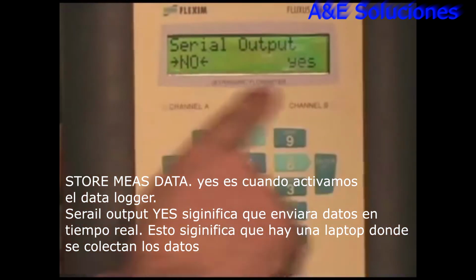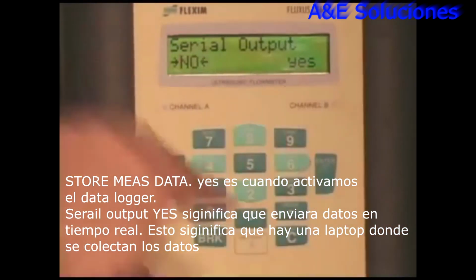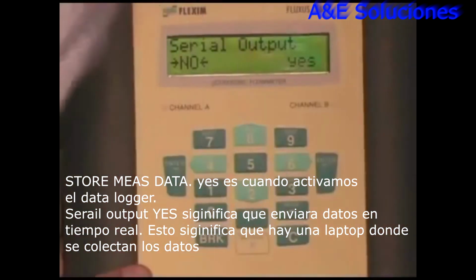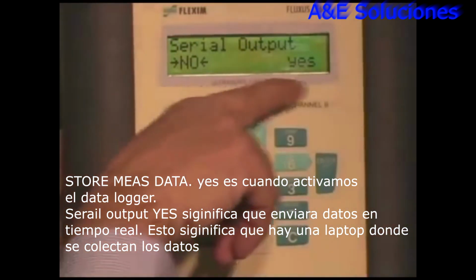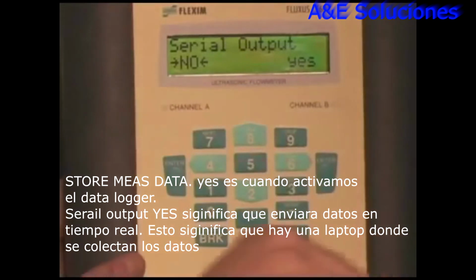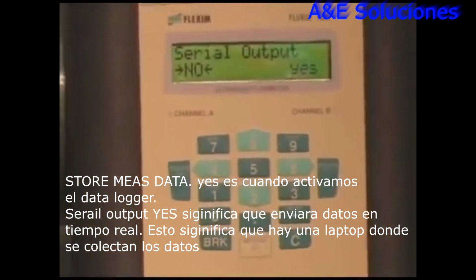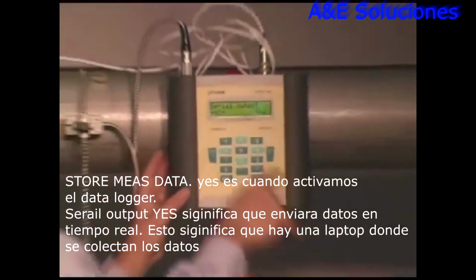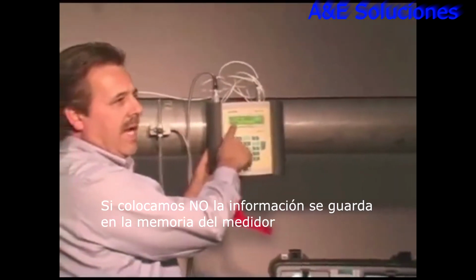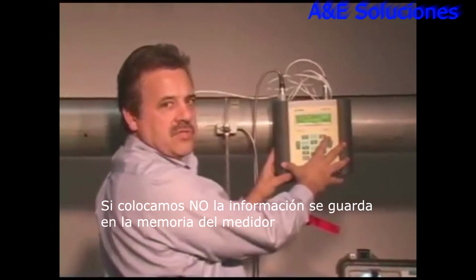Serial output, yes or no. Yes means that it's going out in real time. The serial port is up here on the bulkhead, and yes means that it's going out. The only time you would choose yes is if you have a laptop and you're collecting data directly to the laptop. Otherwise, you choose no, and the data is going into the meter storage.